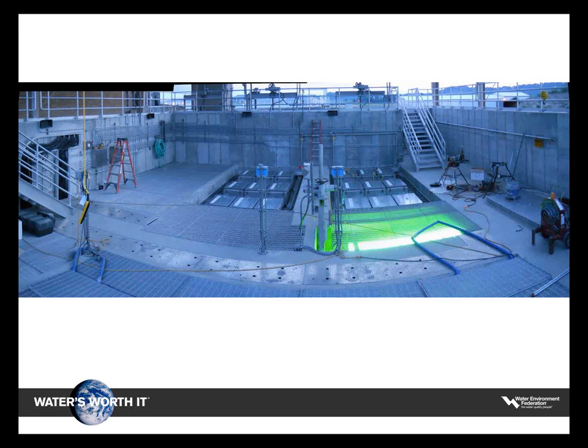This is a photo of Channel 2 in operation still. This was some of the pre-testing that we were doing. We manipulated our flow in our plant during startup to max flow each basin. We wanted to hit it with a full 33 million gallons to make sure that everything responded. We also actually went out of our way to run our suspended solids up.